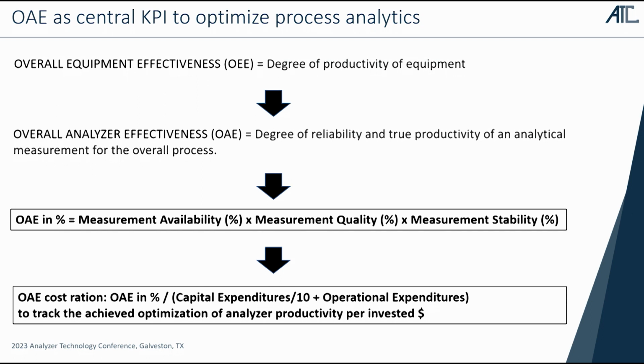It's the overall equipment effectiveness, which is well established in the field of machines and assets, and which describes the degree of productivity of any kind of equipment. Now, using this KPI, which is more used on machines, and transferring it to analytics, of course it means that we have to consider some of the elements, and those are availability, quality, and stability. With this information, we calculate the overall analyzer effectiveness, and later in the presentation you will see a calculation for that.